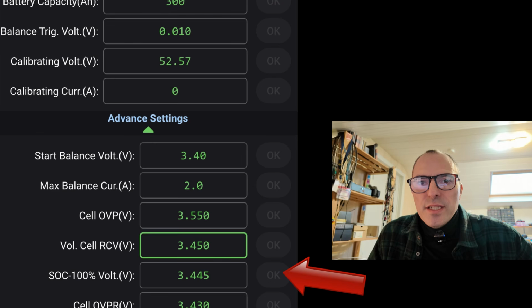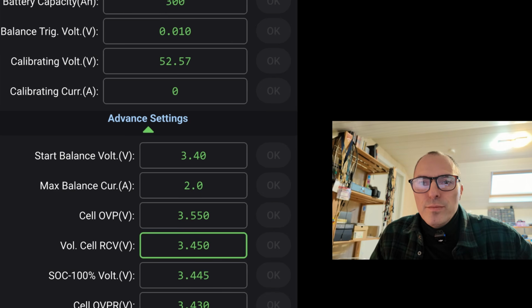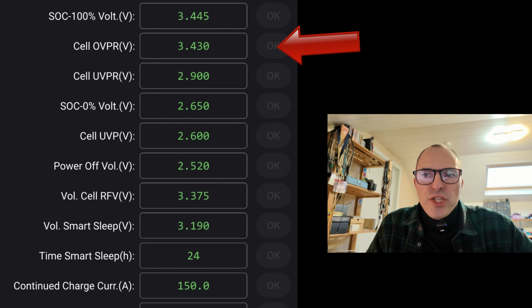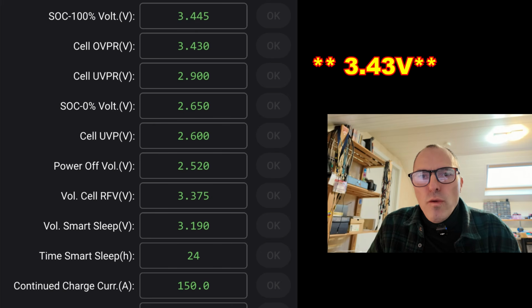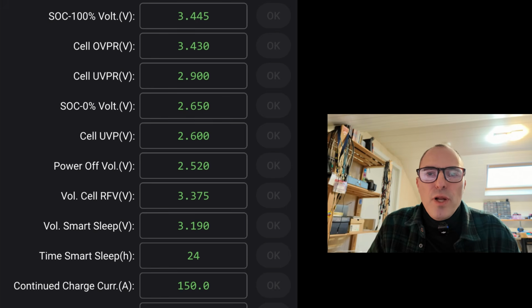SOC 100%. I'll set 3.445 volts. When the system or one cell hits that voltage, 3.445, the system will report a state of charge of 100% and set the remain battery value to 100% in the main menu. Cell over voltage protection return. When the voltage drops below 3.43 volt, the battery will accept a charge. This 3.43 volt might look a low voltage, but even with a relatively small load, voltage will quickly drop below this voltage.